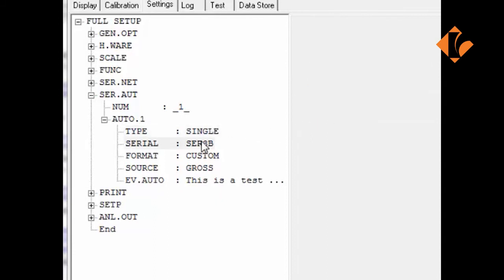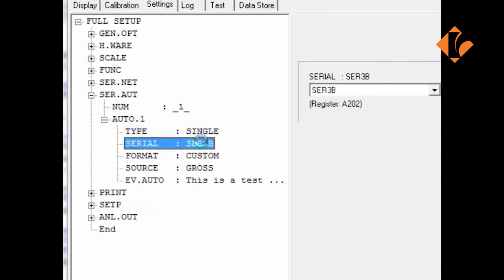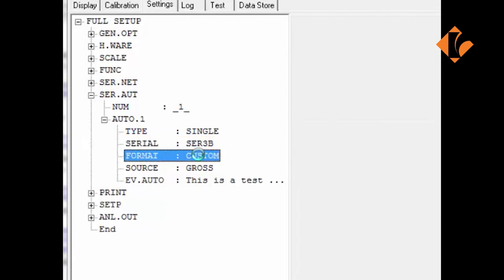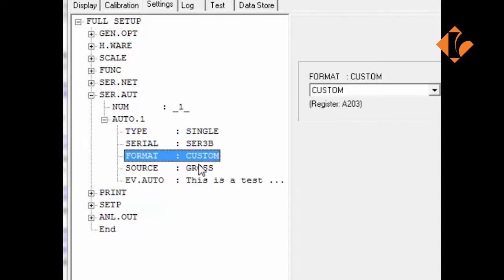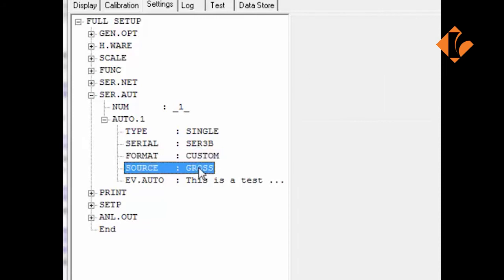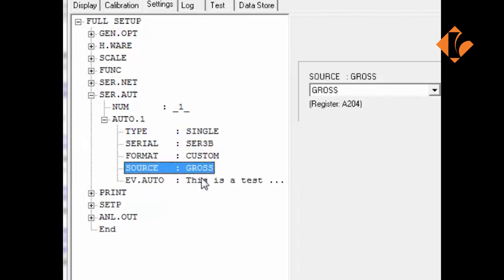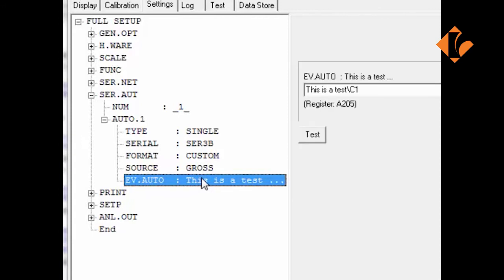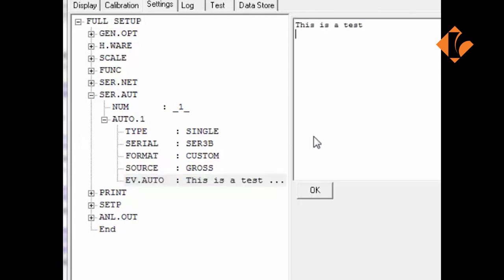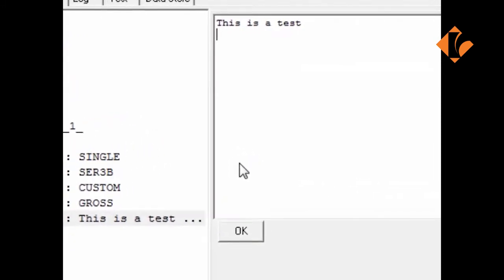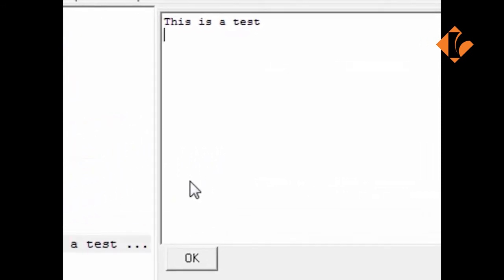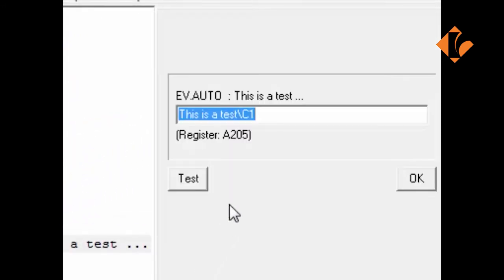We will be outputting via the 3B port, which is the Ethernet port requiring the Ethernet module. We will be sending a custom format, the gross weight and the message we will be sending is this is a test. In this example, the custom event auto is used. The event auto screen is a user-defined screen and basically the information can be entered as required. The backslash C1 token is a newline token.